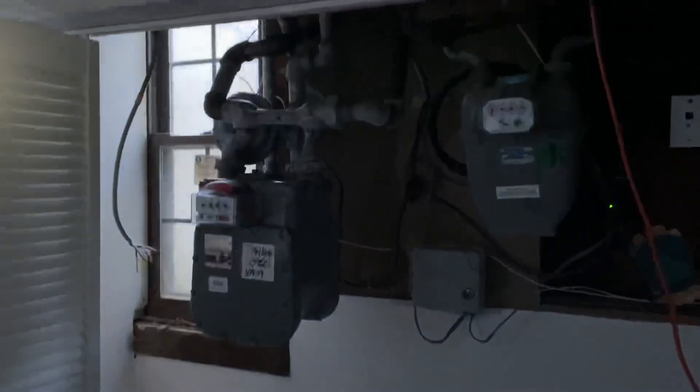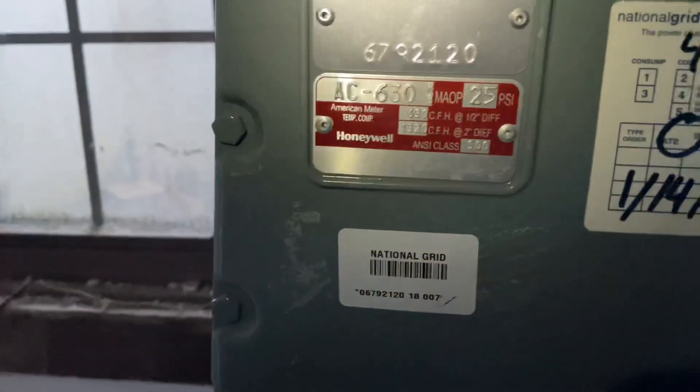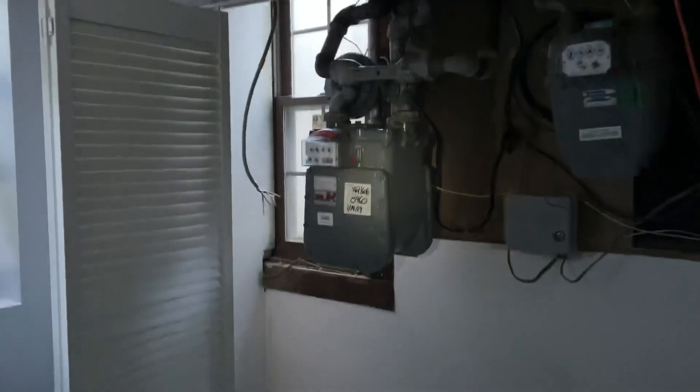There's something wrong with the gas. This is a fairly large house — that's for the guest house. This meter, which is 630,000 BTUs, should be sufficient, but they also added a generator. Anyway, National Grid increased the pressure on the regulator and that solved the gas pressure problem.